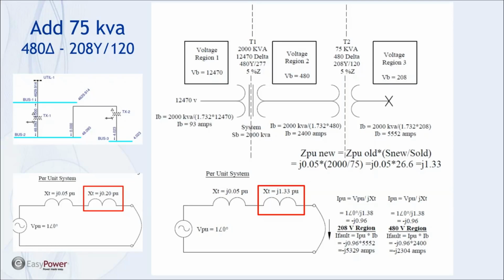You're welcome. More questions? Yeah, there is one more. Very interesting presentation, how to reduce short circuit current with small transformers. Is it economically better than using higher capacity low voltage breakers? I'm not sure if I understand that one. It's a European question, would you read that again? This is coming from our friends in Croatia. It says, how to reduce the short circuit current with smaller transformers. Is it economically better than using higher capacity low voltage breakers? I think the suggestion was the reason we're doing this is to use lower capacity breakers in the low voltage system, and that's not necessarily the case.